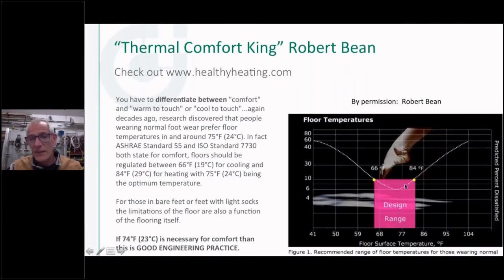And so that's going to dictate the output of this slab. Again, it is the maximum temperature I can get on the surface of that. Now, know that I showed you on this one and that other FEA I showed you a little bit earlier, that's going to vary across the surface area of the slab depending on the spacing of the tube. So if you've got 12-inch on center spacing, that high temperature is going to be right over the tube where it is, and it's going to get a little cooler between the tube until you get to the next one.